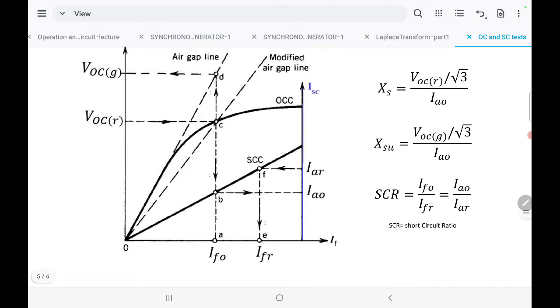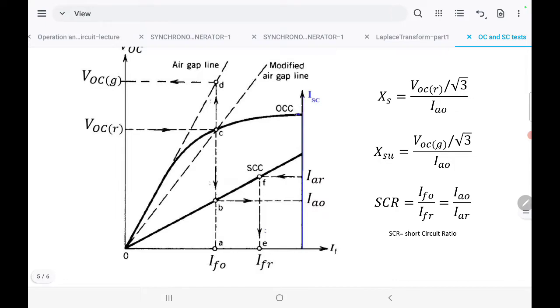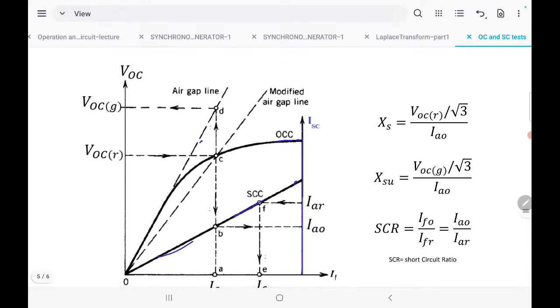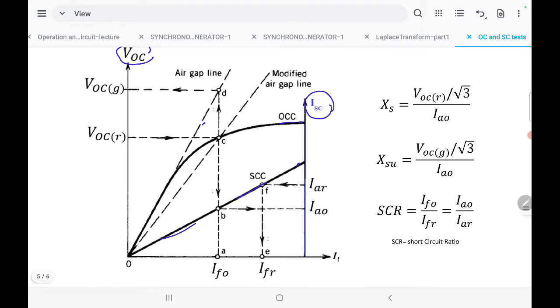It is a good idea to plot both characteristics on one graph. The magnetization curve from the open circuit test and the straight-line air gap line are on the left y-axis (open circuit voltage), while the short circuit line is on the right y-axis (short circuit current). First, find the rated voltage of the machine — for example 208 V line-to-line — and locate that point on the open circuit characteristic.